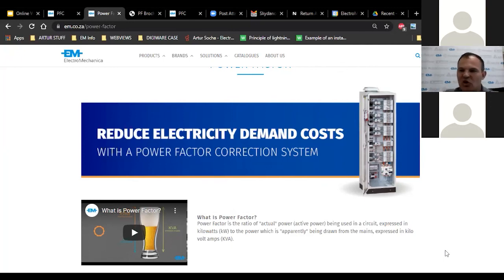But now if I use that same example, and instead of using star deltas, he just put VSDs everywhere, which reduced his demand, which I'll agree to, but now has created another problem. Maybe he had a solar plant. Now the solar plant keeps disconnecting because of bad harmonics. Then you've got to look at active harmonic filtering and try to bring it as close as possible to the load that's creating that problem where possible. I've also seen scenarios where, due to bad harmonics, gensets don't want to synchronize back.